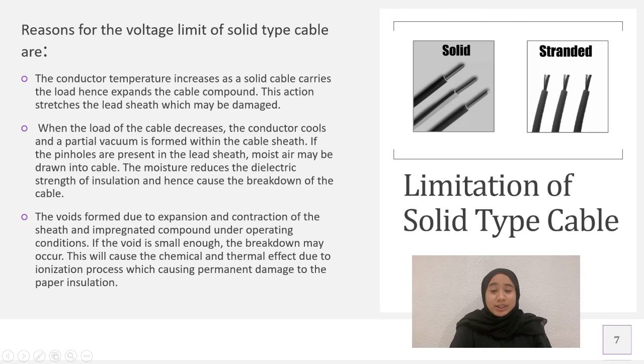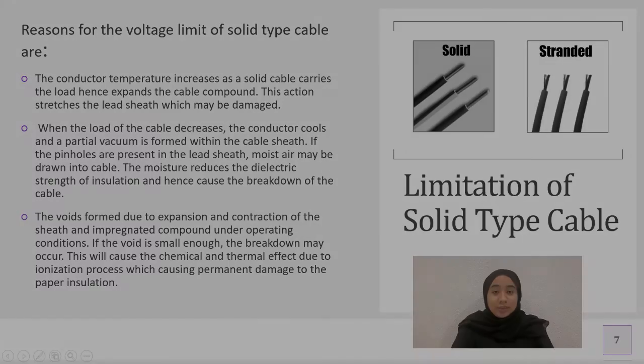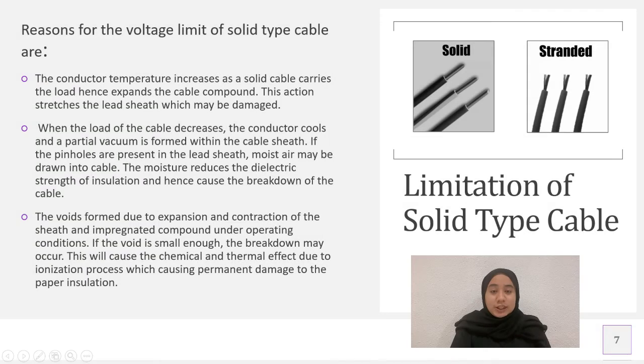So what is solid type cable? Well, basically belted cable and screen cable are also referred to as solid type cable because it uses solid insulation, meaning that there is no gas or oil circulating in the cable sheath. So the voltage limit for solid type cable is 66 kilovolts, and here are the reasons why.